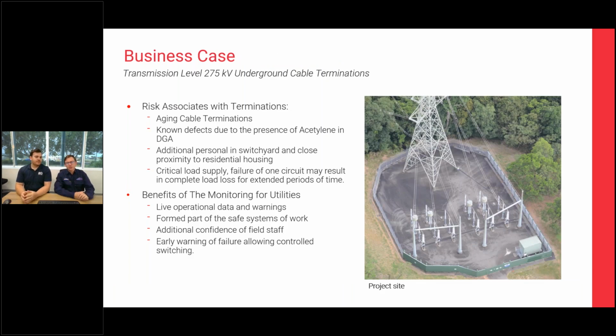Absolutely. So this technology was used in a real-world application. You can see in the image there 2 side-by-side 3-phase 275 kV oil terminations. In the process of our normal routine maintenance, we knew that these terminations were in an aged condition. We did know there was presence of acetylene in the dissolved gas analysis, which leads towards internal activity that's undesirable in electrical assets.